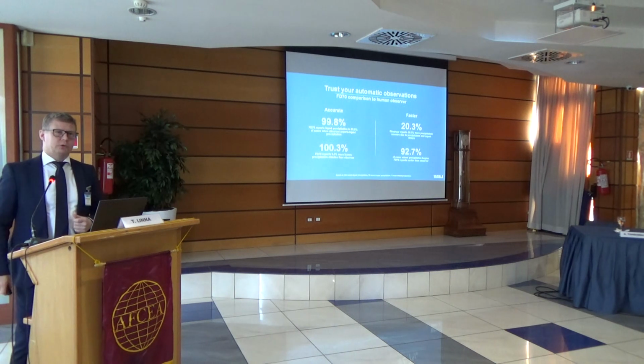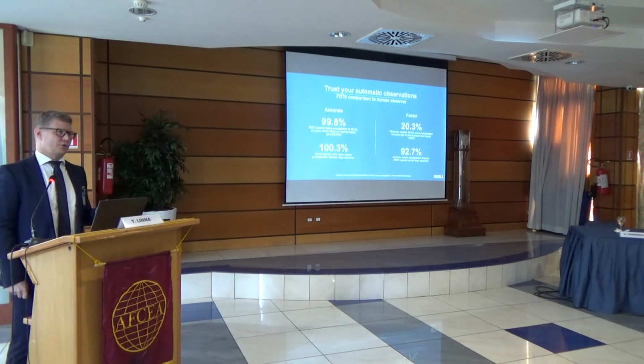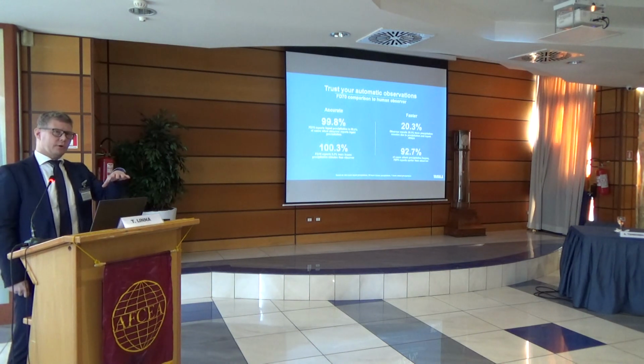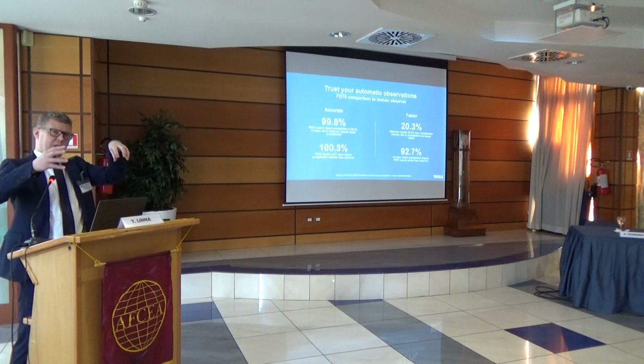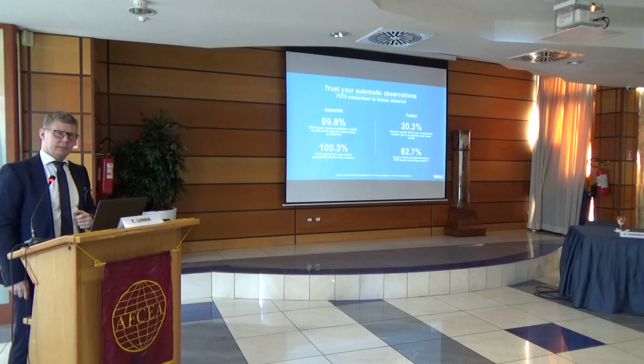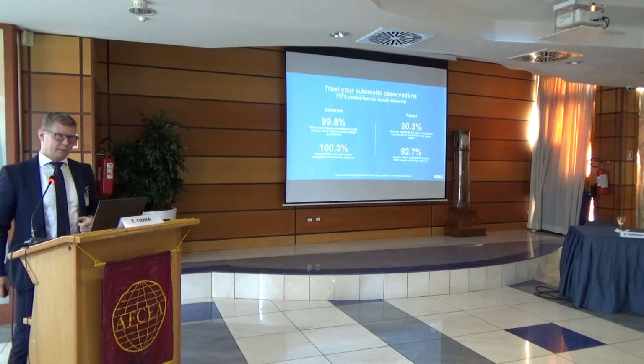We have tested in snow. So basically Helsinki, Vantaa airport, the Norwegian airports, the winter conditions are there like weekly basis in this time of year. We've seen that the wind and snow do not cause extra error on the measurement. In some cases where you can see the error clearly in some experiments, if the sample volume would be higher somewhere in between or shadowed by some structure, then it might cause a problem. But the speed of the particle in that sample plane, we have not seen problems. So basically, in our test field, we have a setup where we have several sensors, FS11, PWD, and FD70 with different rotations so that we can check the wind speed effect there.